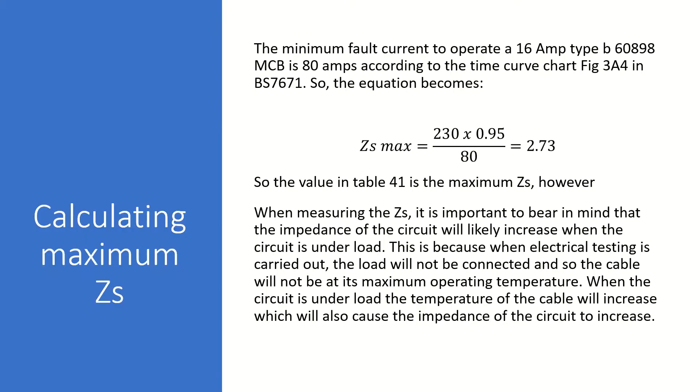So here we have an example of how the maximum Zs is calculated for a 16-amp type B60898 MCB. The value for Ia is 80 amps according to the time curve chart, figure 3A4 in BS7671. So the equation becomes Zs max equals 230 multiplied by 0.95 divided by 80, which gives us a result of 2.73 ohms, which is the same as the figure in table 41.3 in the wiring regulations. So the value in table 41 is the maximum Zs.